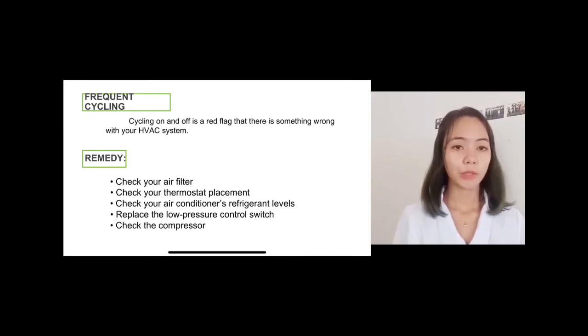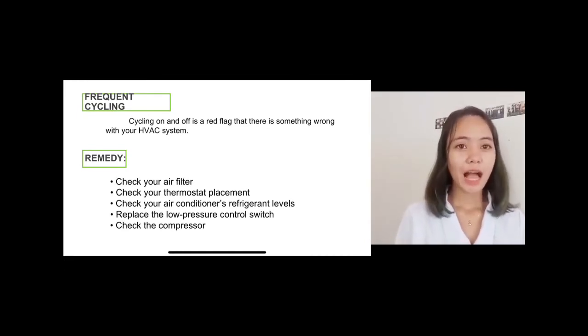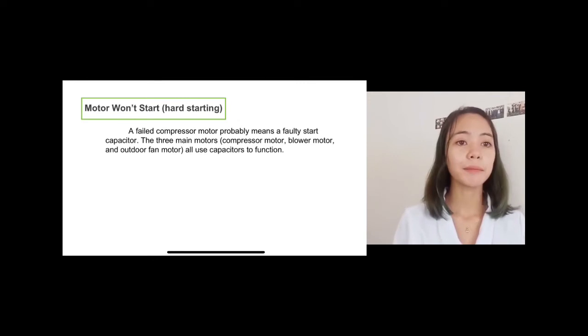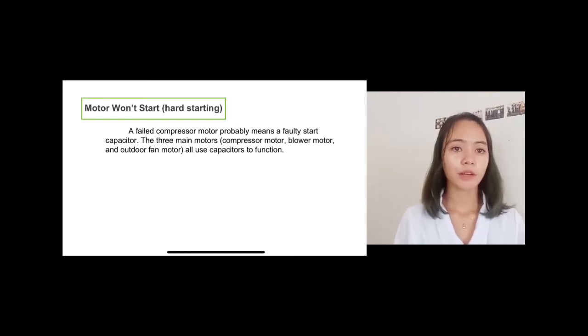Lastly is the motor won't start or hard starting. A failed compressor motor probably means a faulty start capacitor. The three main motors, namely the compressor motor, blower motor, and outdoor fan motor, all use capacitors to function.